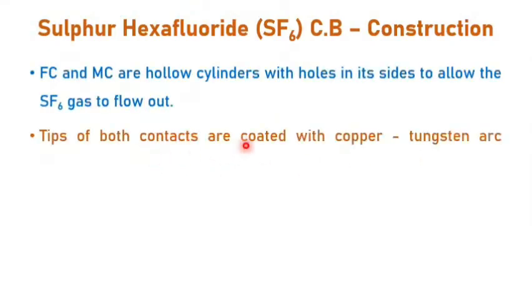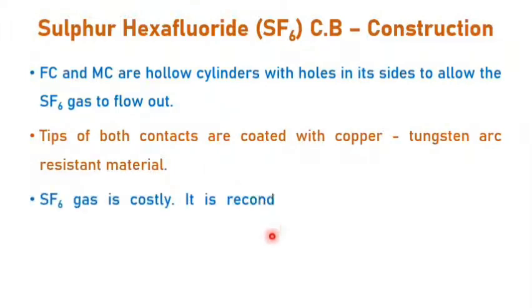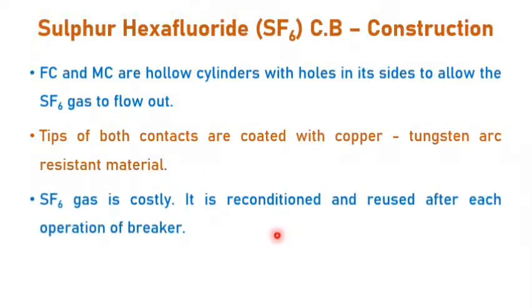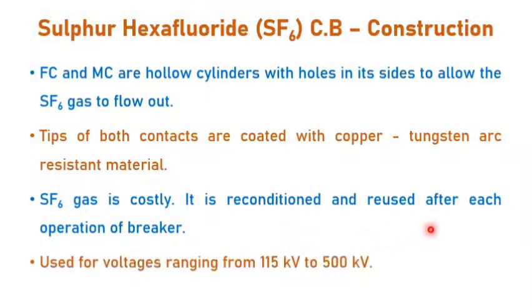So the tips of both the contacts are coated with copper and tungsten arc resistant material so that the contacts will be kept safe even if the arc is struck often. Since the SF6 gas is costlier, we can recondition and reuse it after each operation of the breaker. Unlike mineral oil used in oil circuit breakers, where the oil has to be replaced, here we can recondition and reuse the SF6 gas for multiple operations. Hence it is suitable for high voltage operations, ranging from 115 kilovolt to 500 kilovolt.